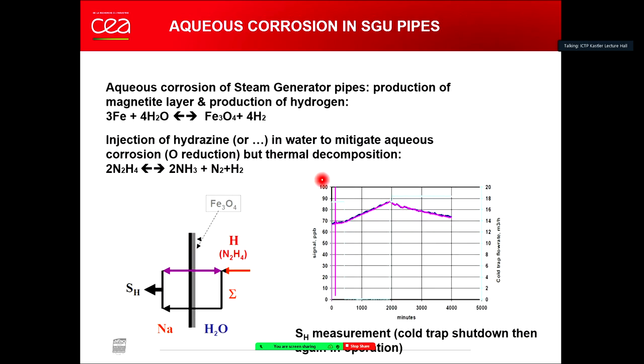You stop, in fact, where the hydrogen is going in the cold traps, okay? It's trapped in the cold trap. So if you want to see what is the source, the best way is to stop your cold traps. And what happens, of course, what you can notice is an increase of the hydrogen content in the secondary.